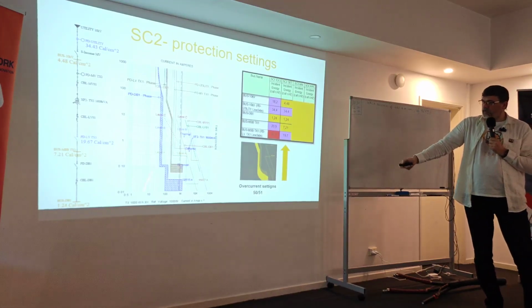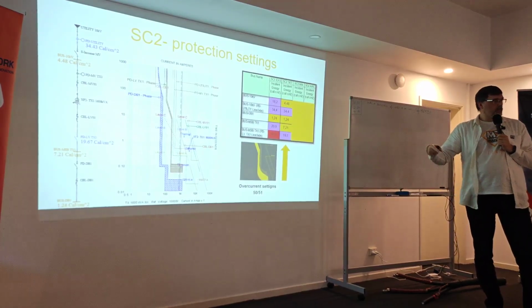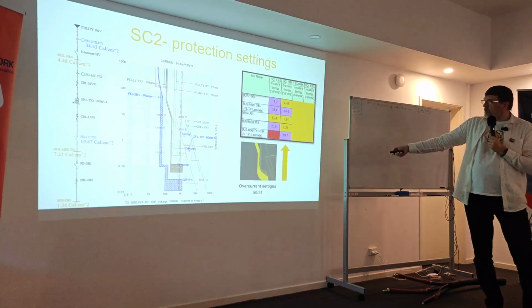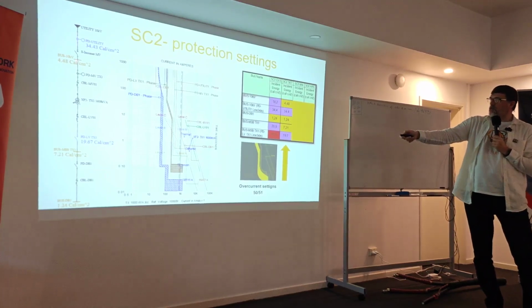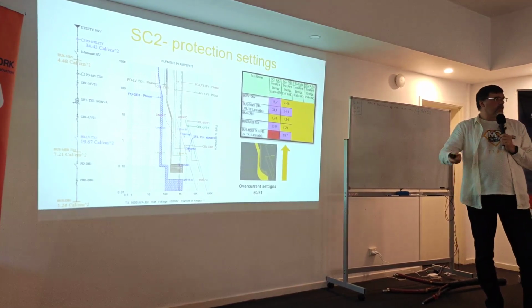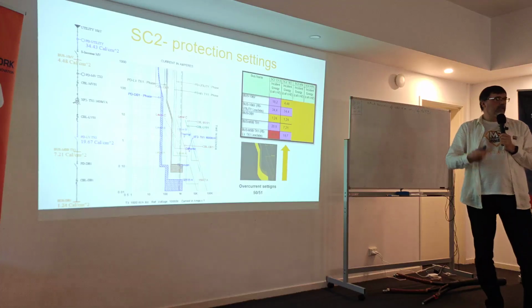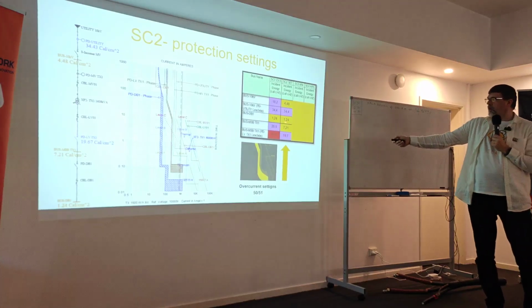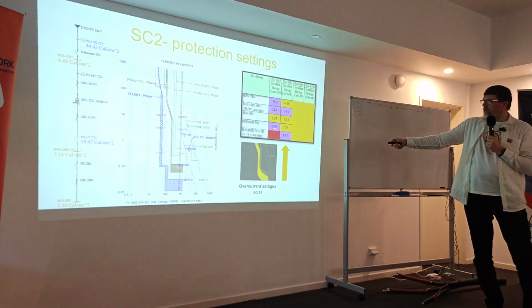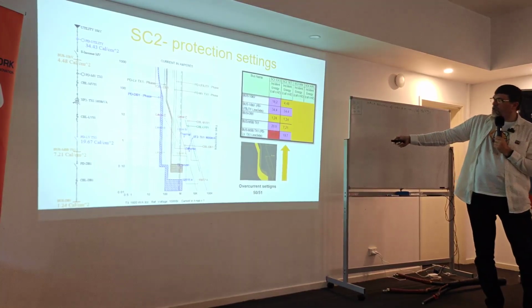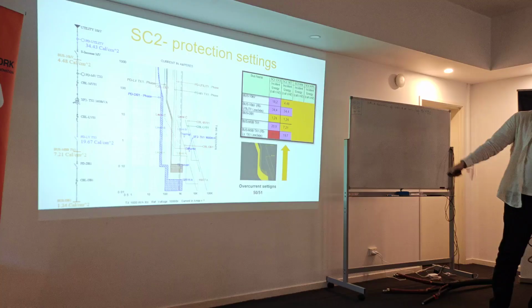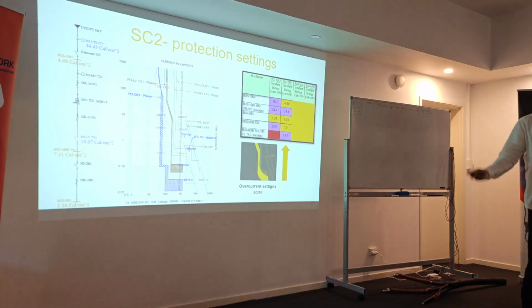But I was able to make it better, faster, even for transformer protection, especially for the medium voltage faults. And then at a certain time we drop the energy. So on 10 kV we drop to 4 calories from 18, which is a huge difference. It's the difference between having 40 calories and 8, yeah? Big difference for the comfort when you are working. On the low voltage, we are already below 8 from 20, and on the incoming from 90 to 19, this is a huge thing already. So you go from sometimes not having PPE to something that I can select, and I can even work comfortably with what we have.